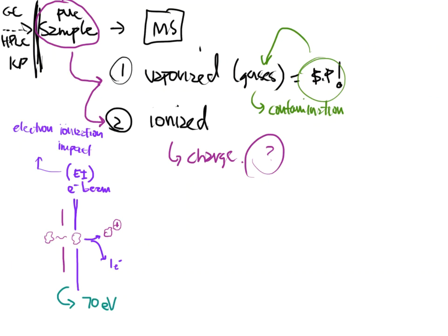All of our databases, all of the mass spectra that we begin to generate and that we begin to reference, they're mainly based on 70 electron volts. So if you go to the SDBS system, the spectral database system, this is where you have been pulling maybe some infrared spectra. There's also an MS category that's going to be listed there in that table for you to choose from. That MS database is all based on 70 electron volts. Now, this can change, but we're changing it for research and development purposes. There is no reason to change it for anything other than that.